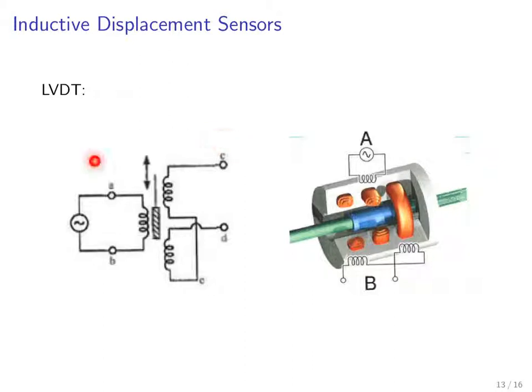The linear variable differential transformer, LVDT, is a device we talked about previously that is widely used in research and clinic to measure pressure, displacement, and force. Here's a circuit schematic. We have a primary transformer with labels A through E. The primary winding is on the left and the secondary windings are on the right. There are two of them. Then you have this slug, this high mu slug, or iron slug that's attached to our stimulus that is moving in and out of the region through which the flux is linking the primary and secondary coils.